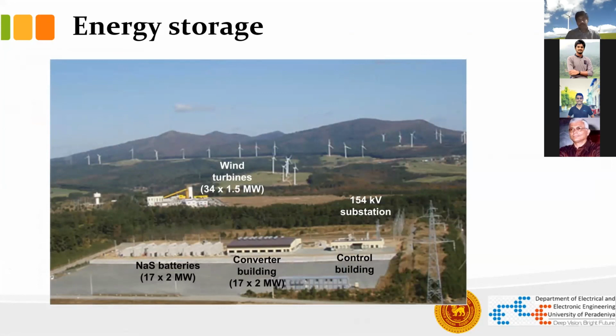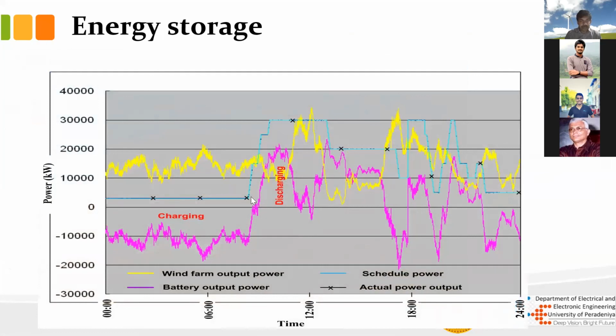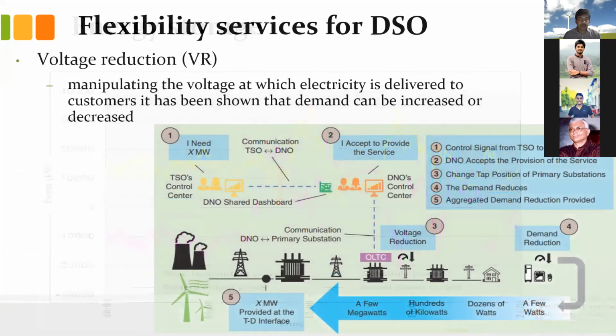This is a power plant in Japan, Rikasho. Again, I may be pronouncing it not properly. It's a wind turbine plant having 51 megawatt of wind turbines, which has a battery bank of 34 megawatt sodium sulfur battery. Now this black line is the dispatch order. The yellow one is the wind farm output. So when the wind farm output is above the dispatch order, you charge the battery and try to keep the total power from that site at the dispatch order. So you can do anything. Your energy storage is pretty fast to achieve good dynamics to achieve this.